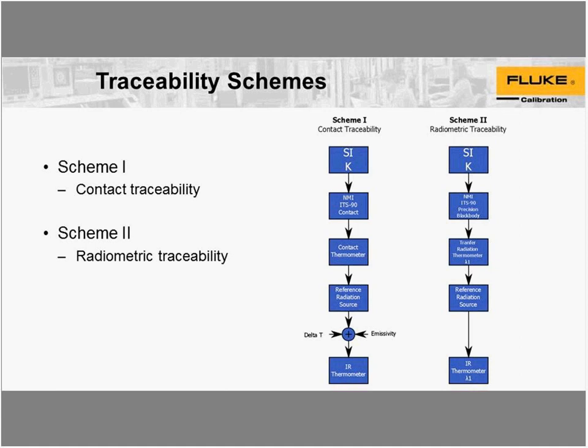For traceability schemes — we're doing traceable work here and we have traceability back to the SI. For contact traceability, we're getting traceability for our thermal radiation source with a contact thermometer — either a PRT, a thermometer, or a thermocouple — which has traceability through a National Metrology Institute to the SI. This contact thermometer is used to get a reference temperature for the thermal radiation source.